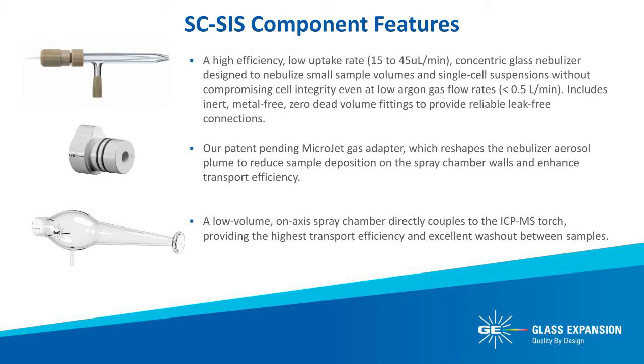The makeup gas flows through Glass Expansion's patent-pending microjet gas adapter, which shapes the nebulizer aerosol plume to reduce sample deposition on the spray chamber walls and greatly enhance transport efficiency. This is the key to providing such high transport efficiency, as other systems simply have a makeup gas port which provides little to no effect on the aerosol plume, resulting in much lower transport efficiencies.